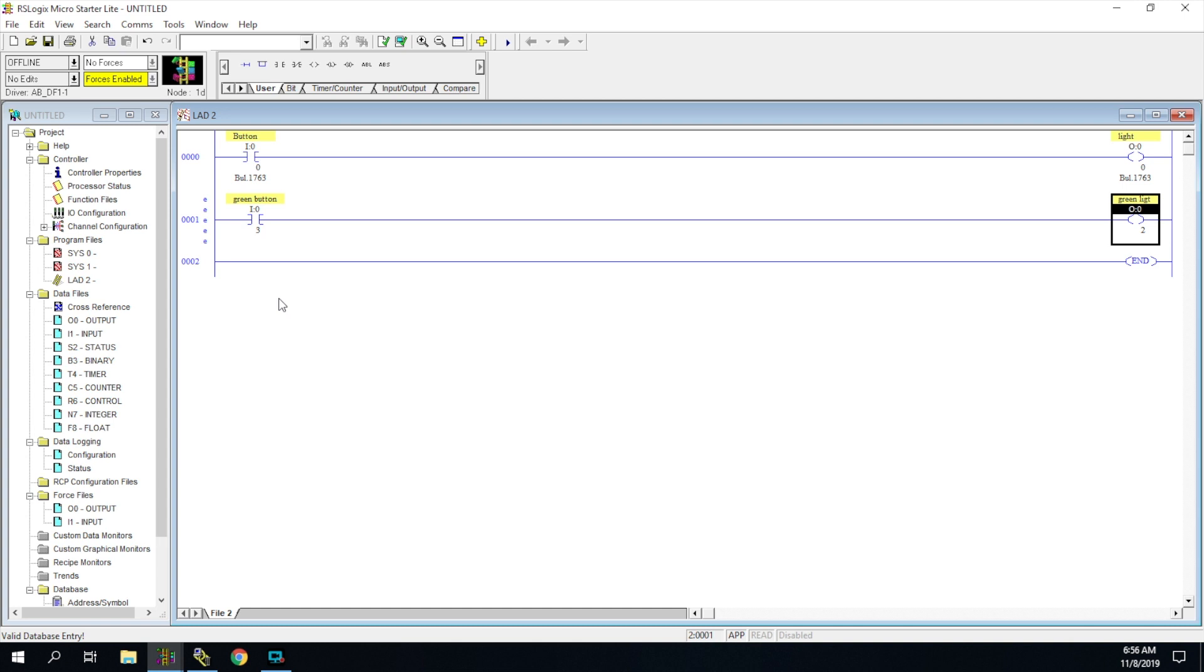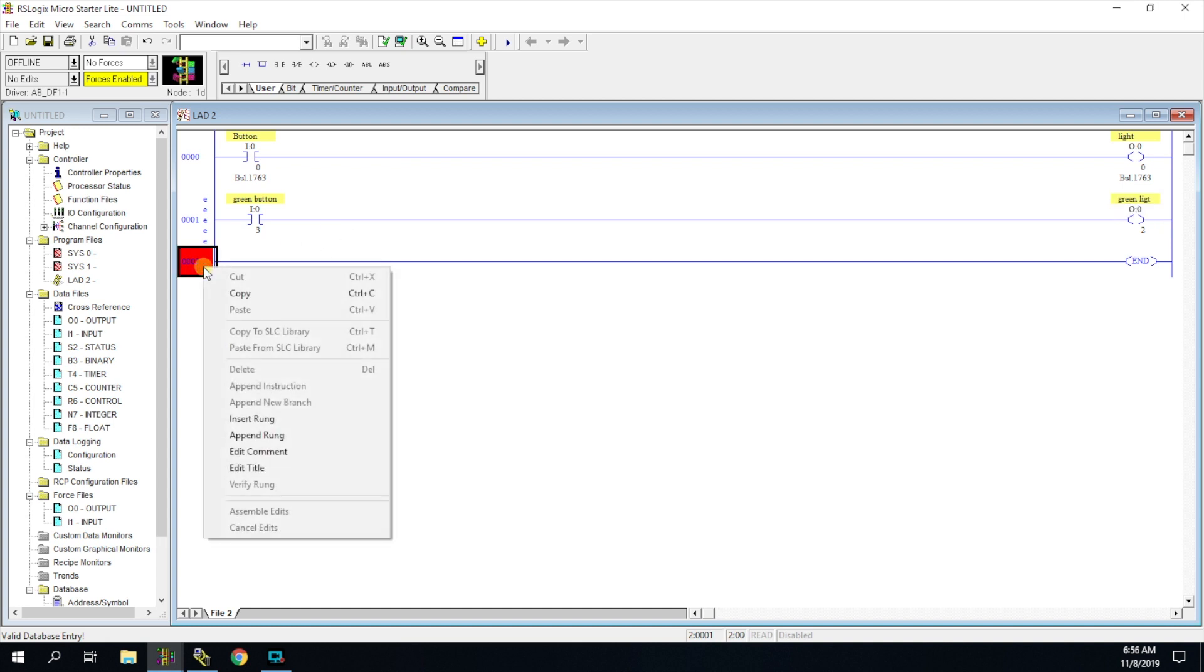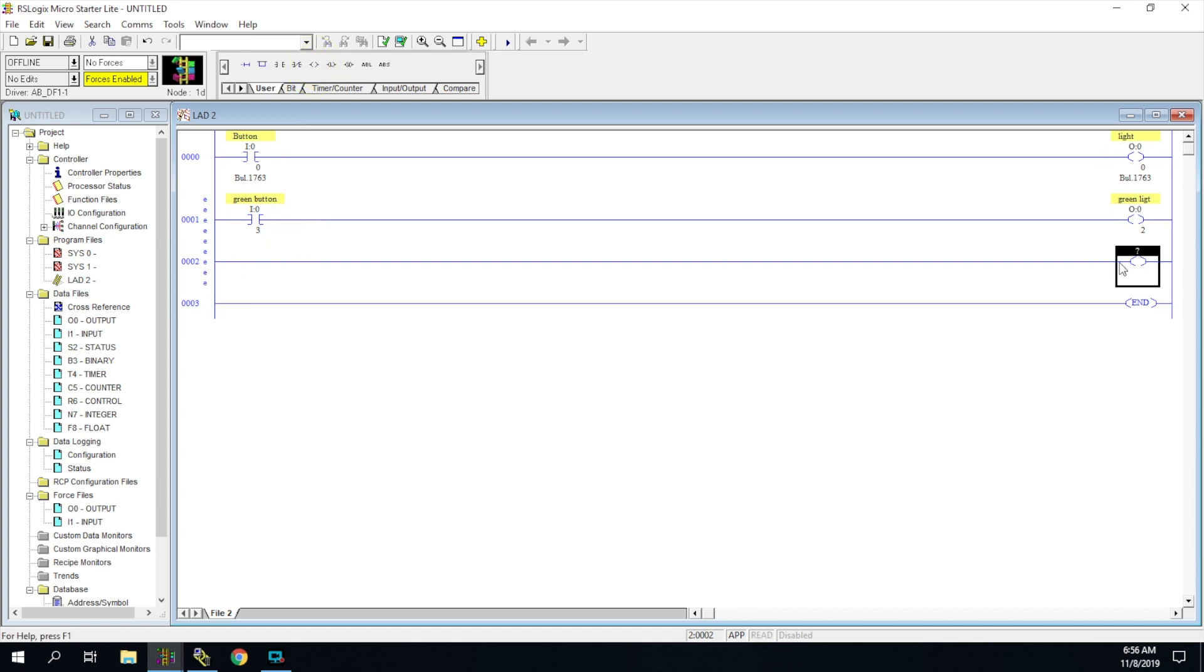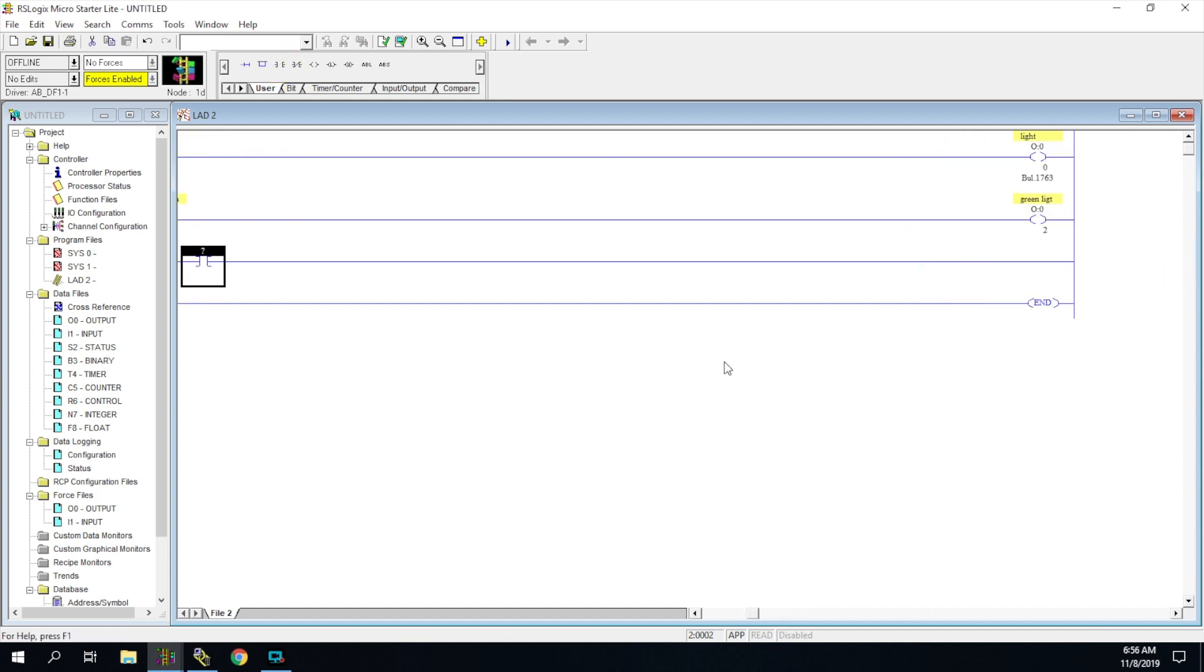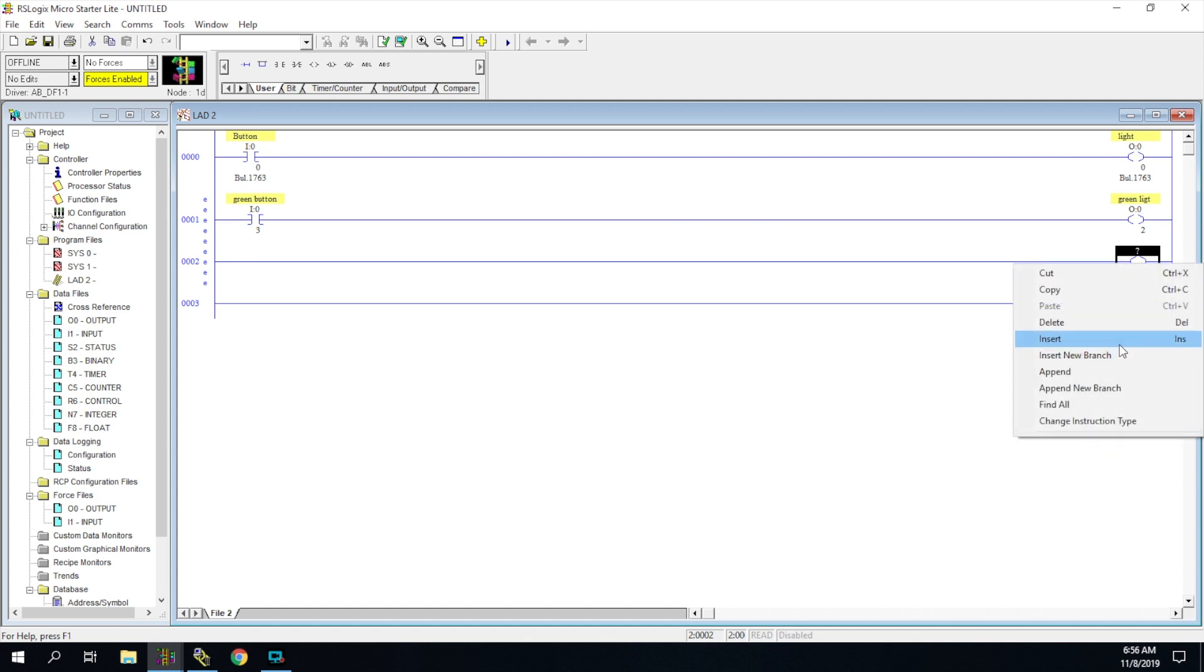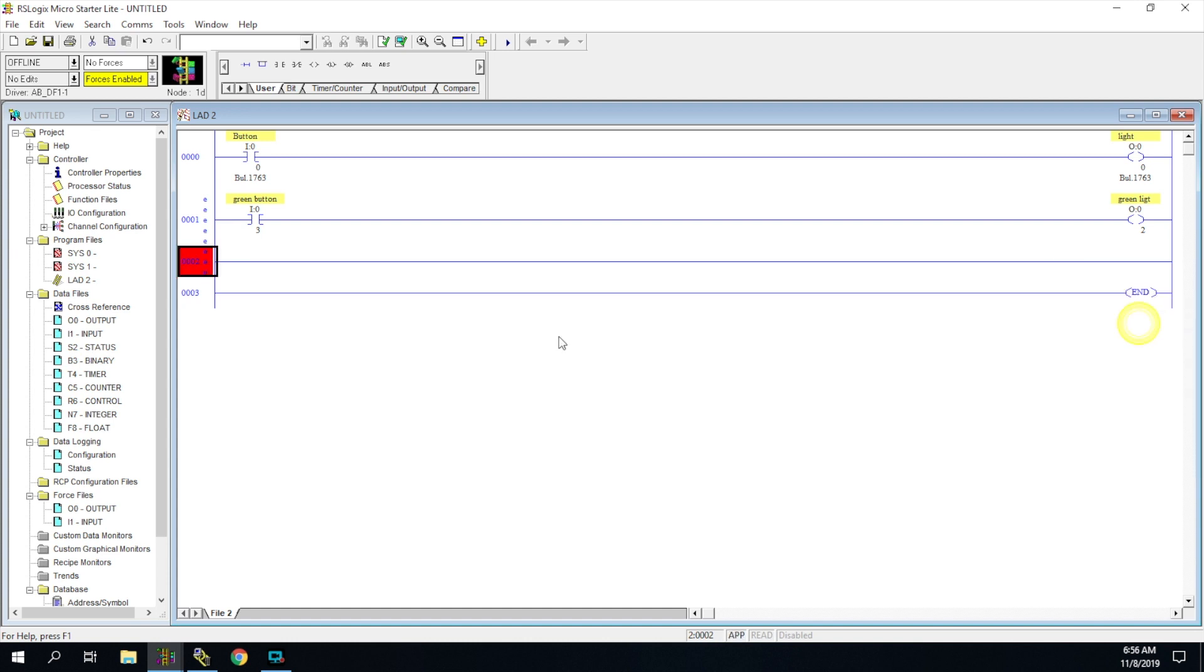The second thing I want to talk about is where the instructions are going to go on these rungs. So if I was to append a rung here and add it in, and the first thing I put was an instruction or an output, it magically pulls it over here to the right. But I could take an instruction now that we've already got it laid out and I could force that OTE over to the left. This is not something you want to do, it will never work. So I'm going to go ahead and delete these. We always want to make sure that this stuff on the left is going to be your instructions, your XIOs, XICs, things like that. All of your outputs are going to be over here on the right side.